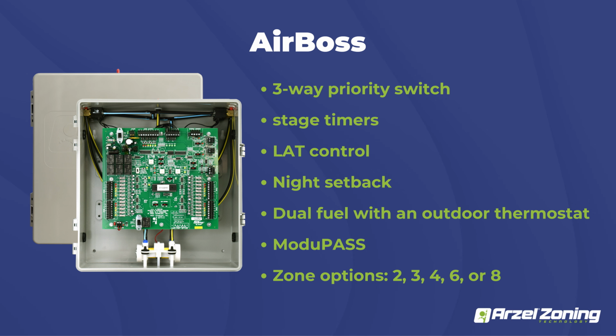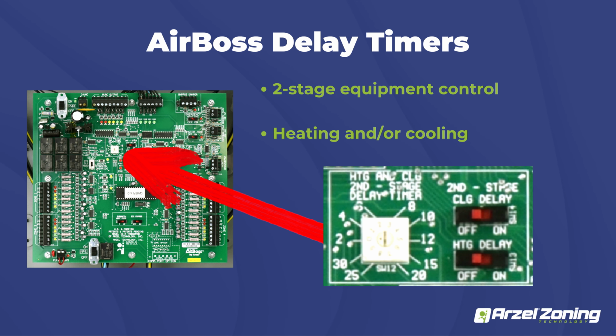And this panel is going to come in either a 2-zone, 3-zone, 4-zone, 6, or 8. So if you have those larger jobs, it's definitely going to accommodate for that. If you guys are doing 2-stage equipment, you have 2 different options with the AirBoss. You can either use 2-stage thermostats to do your capability for that second stage, or if you don't want to run the wires for the thermostats, there are delay timers built onto the board. You can set those anywhere from 2 minutes up to 30 minutes. And after that amount of time elapses, it's going to engage that second stage operation.